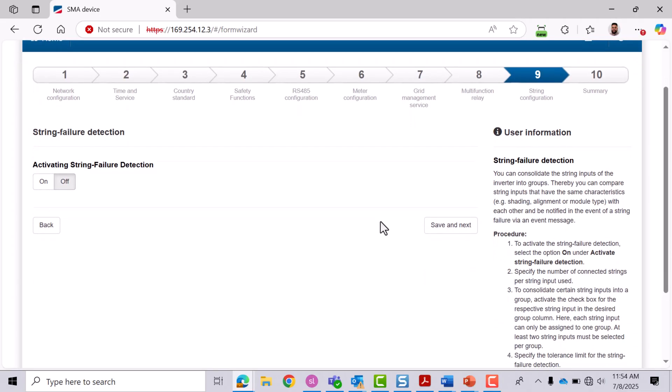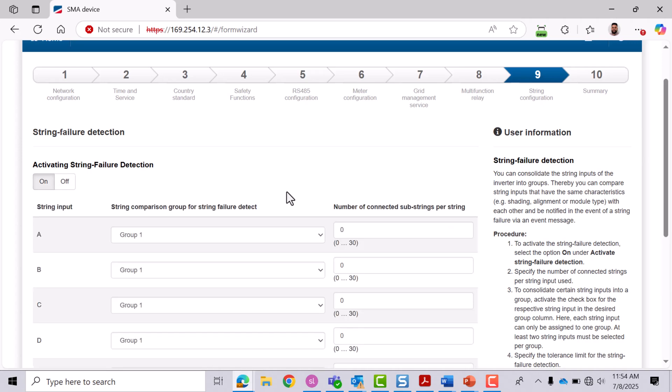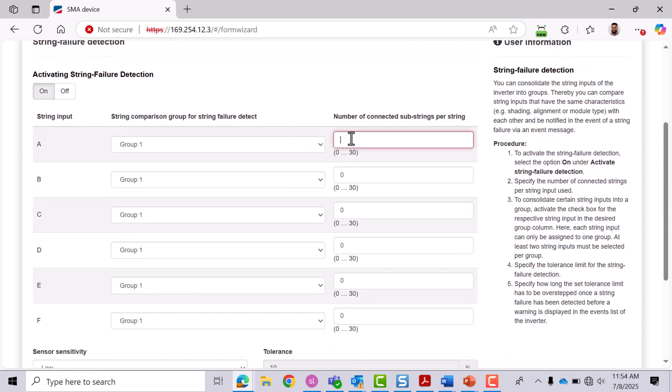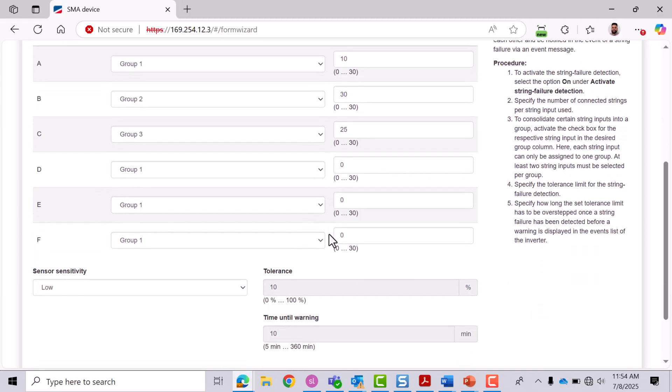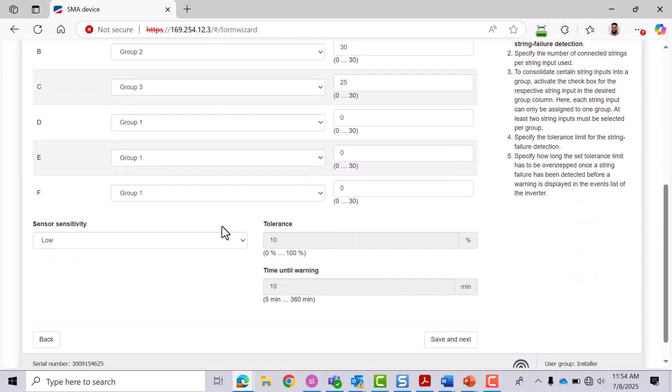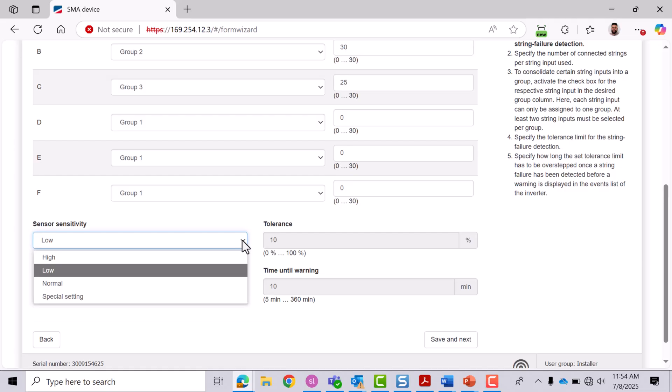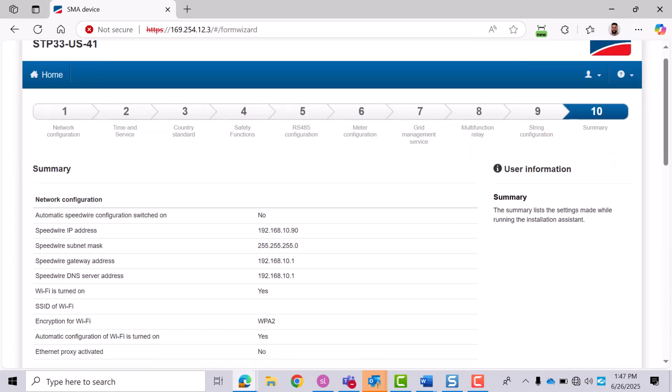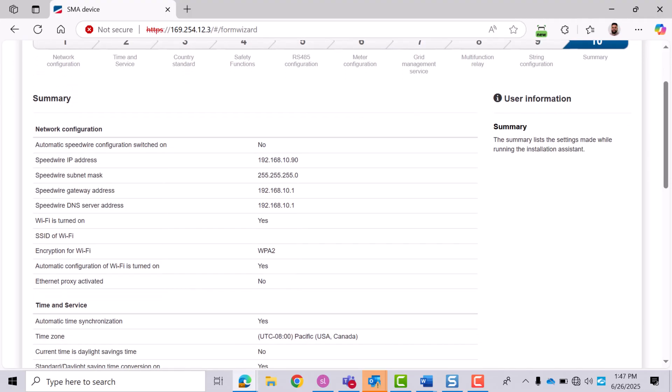This feature helps identify underperforming strings by comparing inputs with similar conditions like tilt, shading, or module type. It's off by default. Click On to begin. Assign each input to a group, enter the number of strings, then choose a sensitivity—either a preset or special setting—to define tolerance and time. This ensures you'll be alerted if a string's performance drops unexpectedly. Click Save and Next.